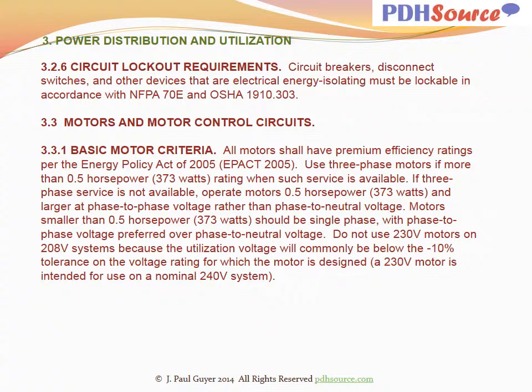Use three-phase motors if more than 1/2 horsepower, 373 watts rating, when such service is available. If three-phase service is not available, operate motors 0.5 horsepower and larger at phase-to-phase voltage rather than phase-to-neutral voltage. Motors smaller than 1/2 horsepower should be single-phase, with phase-to-phase voltage preferred over phase-to-neutral voltage. Do not use 230 volt motors on 208 systems because the utilization voltage will commonly be below the -10% tolerance on the voltage rating for which the motor is designed. A 230 volt motor is intended for use on a nominal 240 volt system.